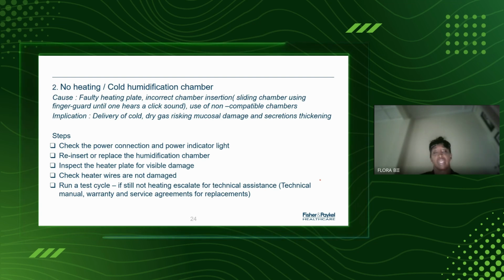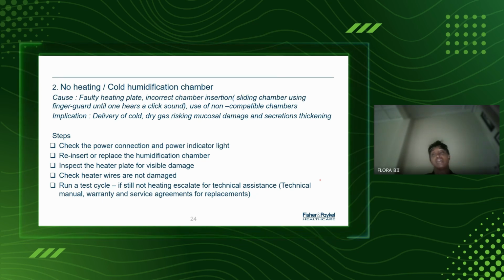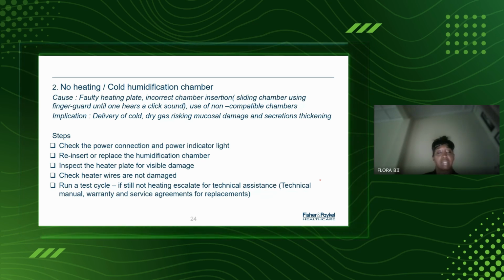Some would be no heating, or where you have a cold humidification chamber. In this case, it would be either a faulty heating plate, a chamber insertion that has not been done correctly, or just the use of non-compatible chambers. This would imply delivery of very cold, dry gas, essentially not providing active humidification. Several steps can be taken there.